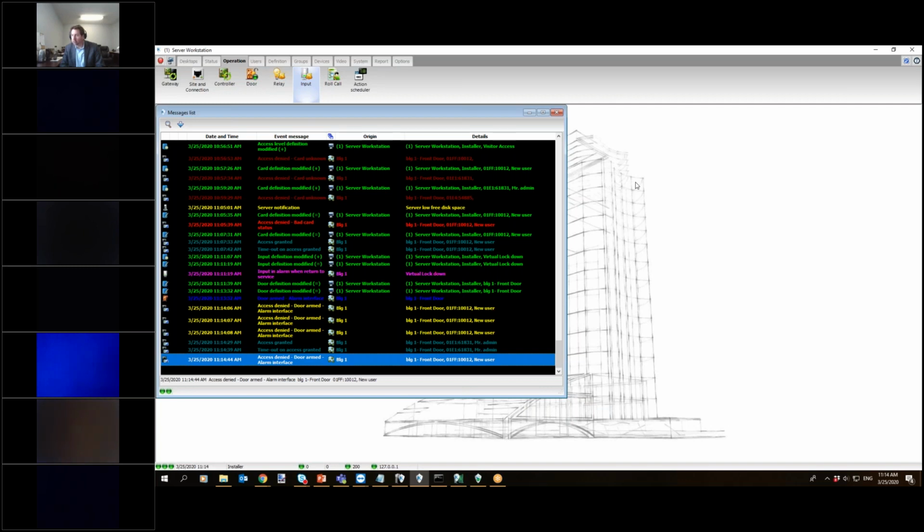So this is my preferred one. Why? I don't change cards. I don't change door programming other than input. It's instant and it's hardware based. It really relies on the controller, but it also gives me the ability to let certain people get in without having to do massive changes, right? And it applies to almost all the versions and almost all the controllers, except for the KT200s, unfortunately, right?